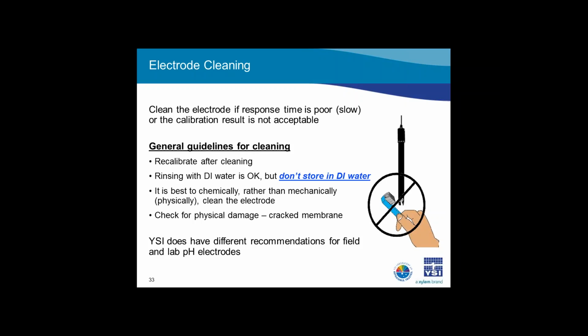As a general rule for pH electrodes, it is best to perform a chemical cleaning on the electrode and not a mechanical cleaning. The reason for this is because with a mechanical cleaning, there is greater risk of damaging the electrode, and the damage may very well be irreversible. Also, please note that we have different cleaning recommendations for field and lab pH electrodes. I'll be reviewing recommendations for lab electrodes in today's presentation. For information on cleaning field sensors, please review our pH handbook or our previously recorded webinar on pH field measurements.